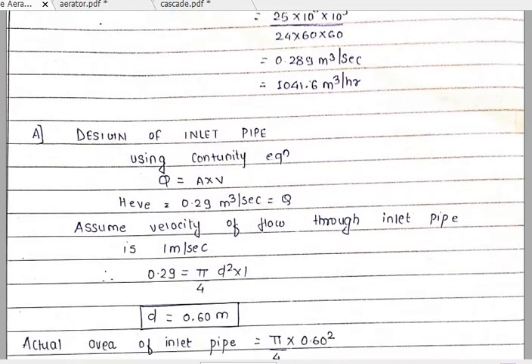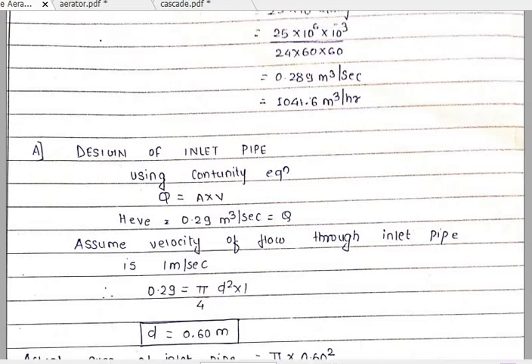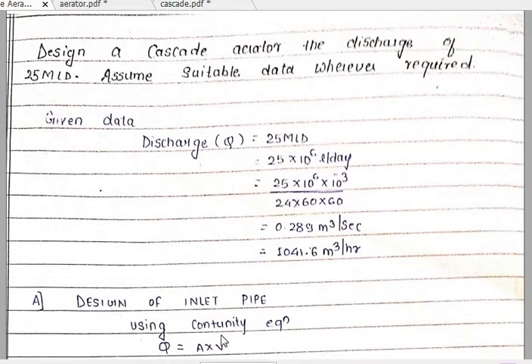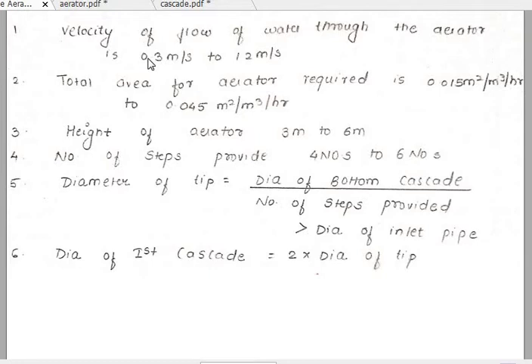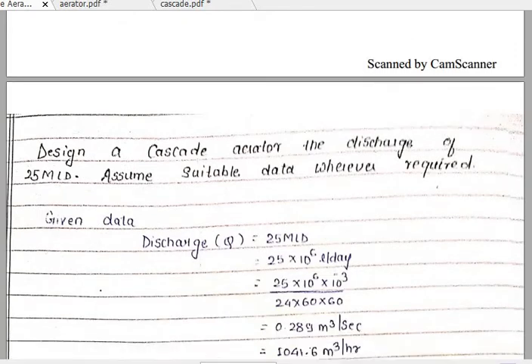To design the inlet pipe we use the continuity equation, which is Q equals A into V, where Q is discharge, A is area, and V is velocity. Here there are two unknowns — we do not know the velocity and we do not know the area. However, the design criteria tells us the velocity of flow of water through the aerator should be 0.3 meter per second to 1.2 meter per second, meaning we can assume any value within this range. So I have assumed the velocity as 1 meter per second.